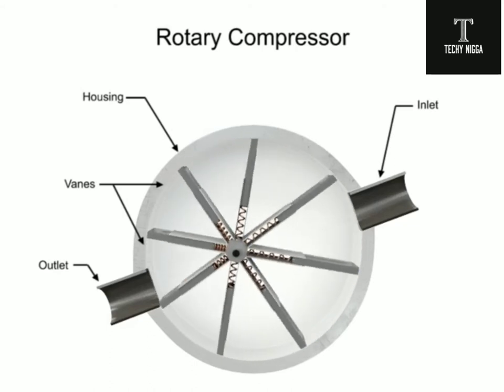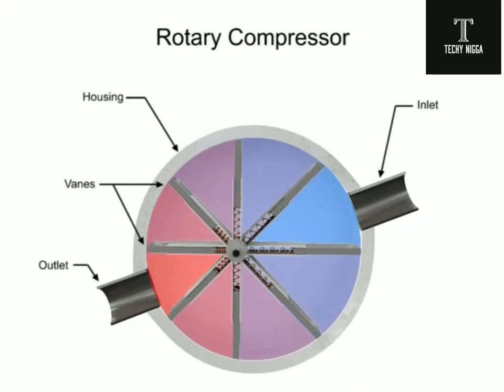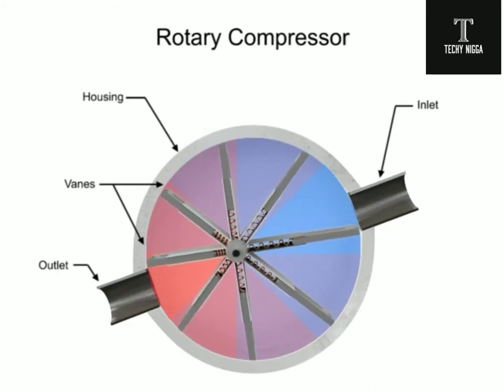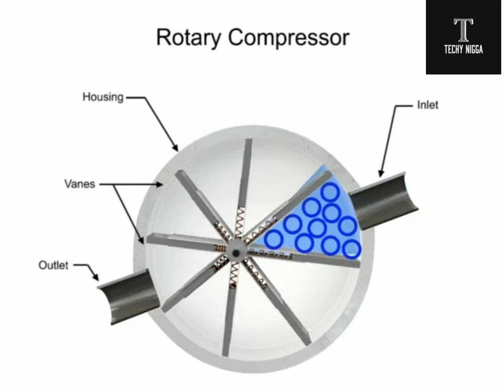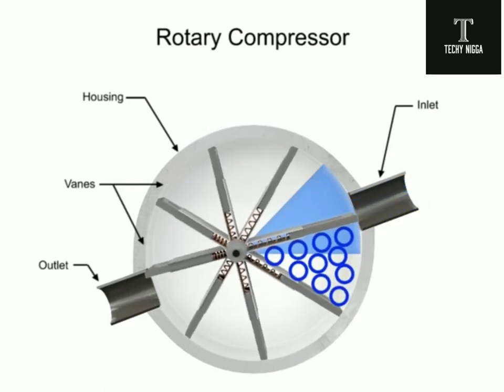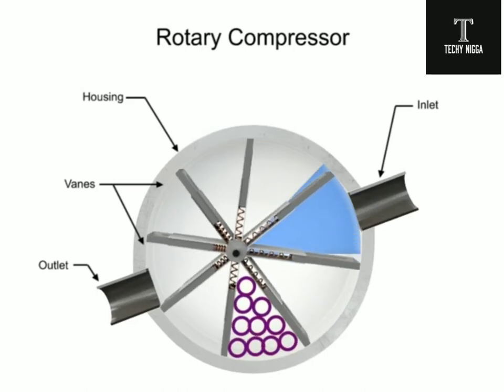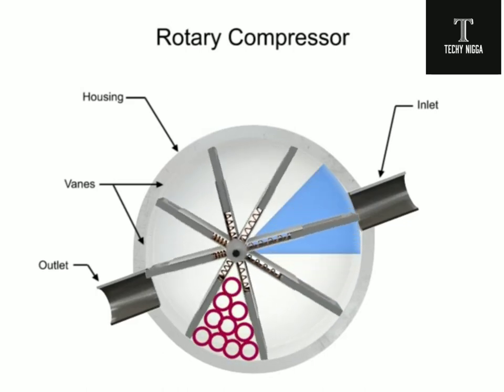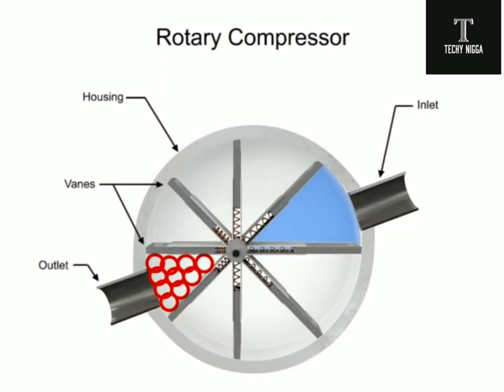As the vanes slide, they create chambers within the cylinder of varying sizes. Air enters at the largest chamber. As the vanes rotate, they retract, causing the chamber to get smaller and compress the air. Air exits at the smallest chamber.